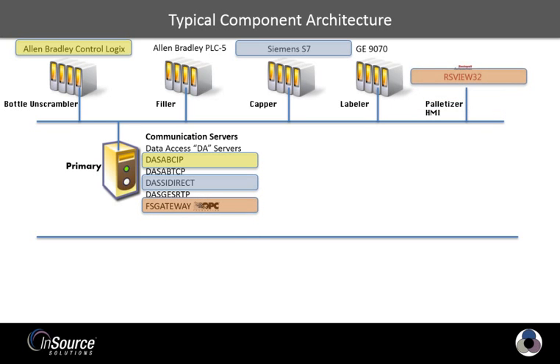Notice that the palletizer is a little different. The OEM has provided a Rockwell RSView application which will remain as local control at the palletizer even though Wonderware is acting as the overarching information management system. In order to get RSView data into the Wonderware system, a connection must be established to RSView via the OPC, or OLE for Process Control, protocol, which is done with the FSGateway DA server. It converts the OPC protocol to the SuiteLink protocol from Wonderware and vice versa for Wonderware applications like InTouch and Historian.